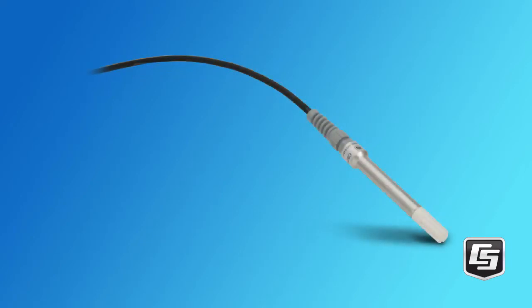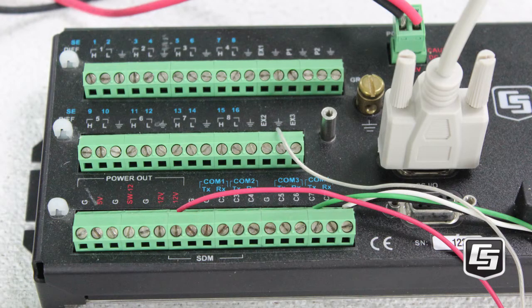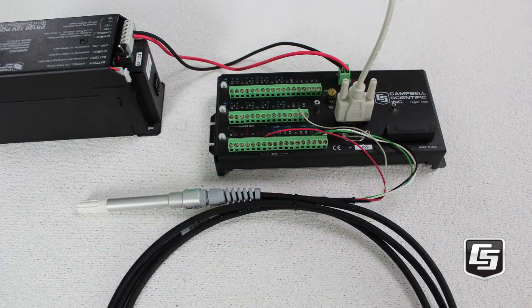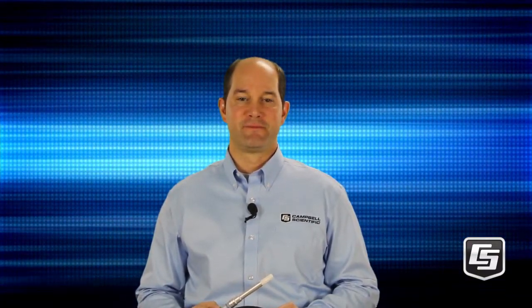In this tutorial, we'll use the CS215 temperature and relative humidity sensor. I'll have it connected to my CR1000 with a green data line to C7. That'll be important to remember. It is powered by 12 volts and grounded appropriately. I also have a serial cable from my computer to the CR1000's RS232 port. I'm running LoggerNet, but you can do this through PC400 and PC200W too, or a terminal emulator program such as HyperTerminal. Let's get started.